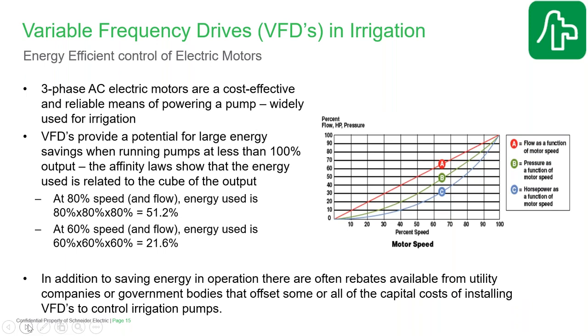One of these tools, as Jack was talking about, for more energy efficient irrigation is the use of variable frequency drives, or VFDs, for irrigation pump control. When you're using an electric motor to run the pump, a VFD is a very good solution for how you control that pump. If you're just running the motor directly, you'll be using a lot of energy if you're regulating the flow, because you'll be using a flow restriction or a control valve to reduce the flow to the required levels.